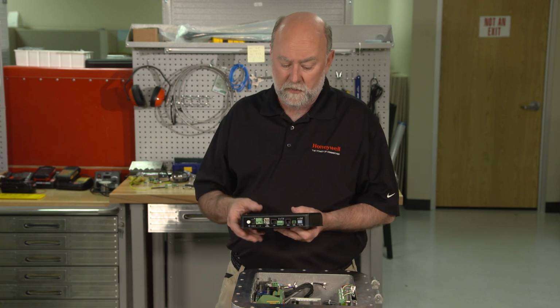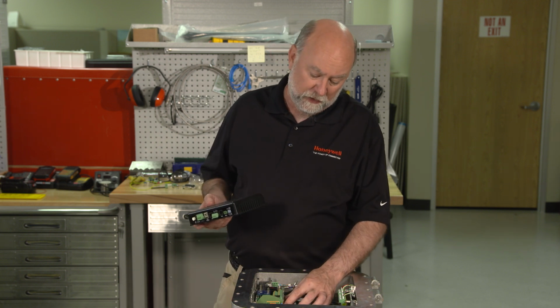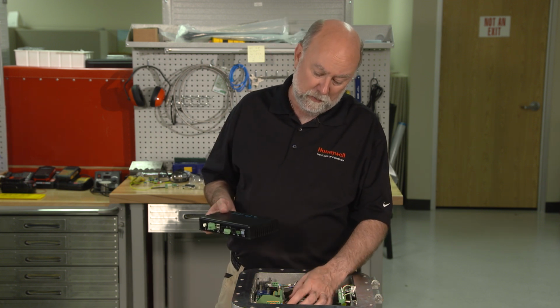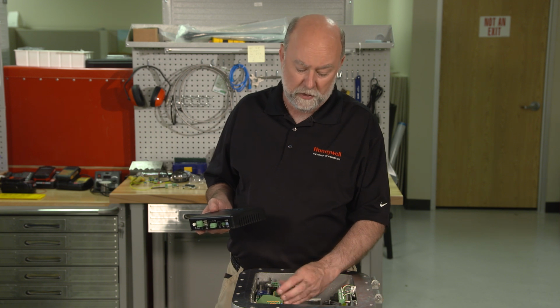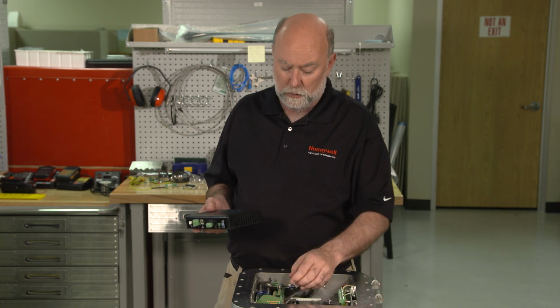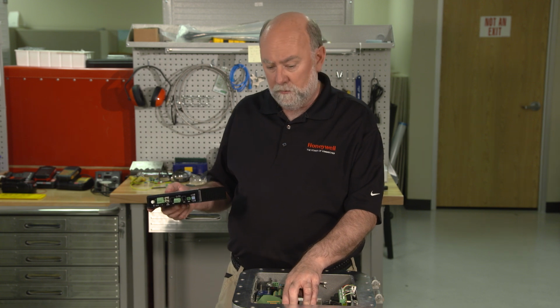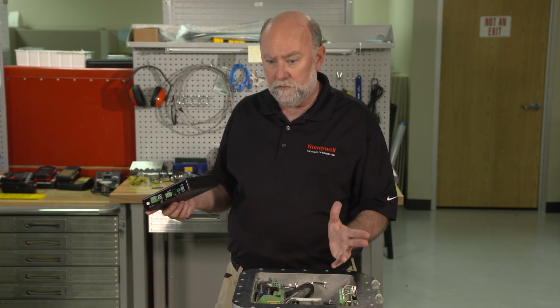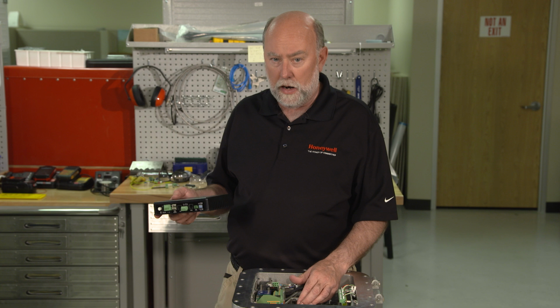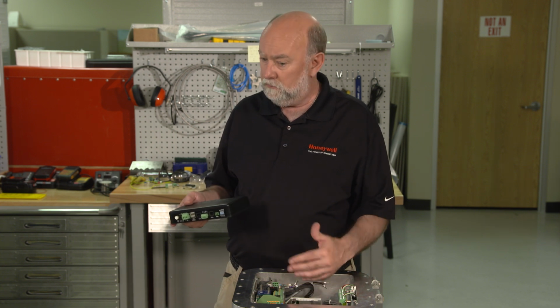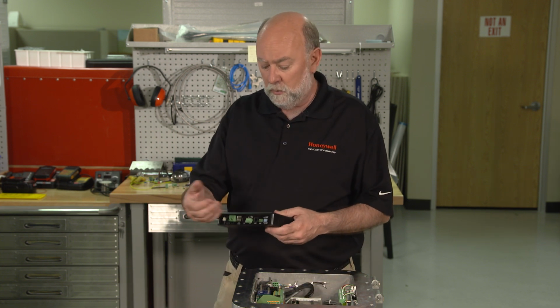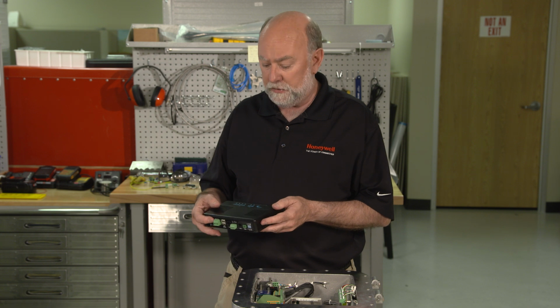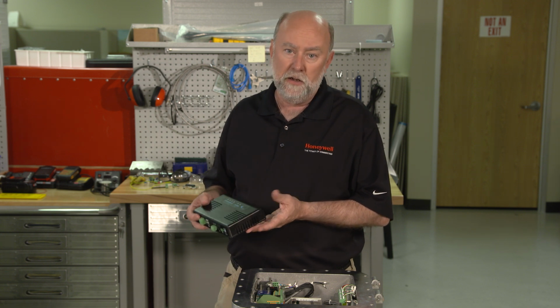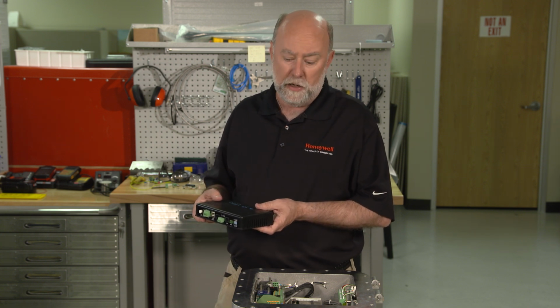That requires this external VDSL modem as well as the internal VDSL modem that lives behind the field terminal board inside of this enclosure. Between these two devices, we can use just ordinary 2 conductor wires, twisted, shielded, unshielded, doesn't matter. We bring that cable into here, we power this box up. This box lives in a safe area where you want to run the laptop with Sonic Explorer.